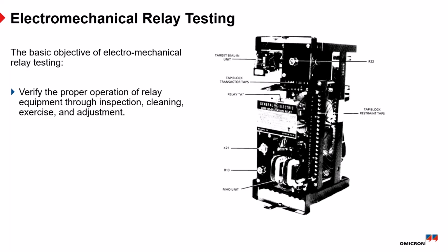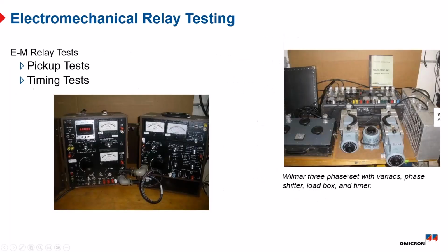But because of the special construction of each electromechanical protective relay, there's frequently some special tests that had to be done too, where you would put in a certain input and measure a voltage at a certain point in the relay and adjust resistors or other components in order to get the desired results. So there was not only a standard pickup and time delay test, but there was also some hardware specific test as well.